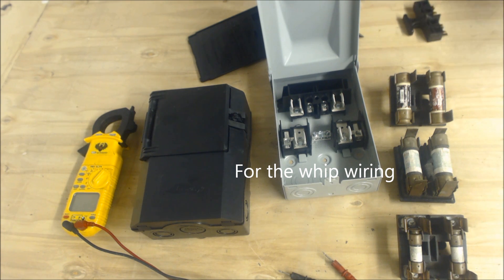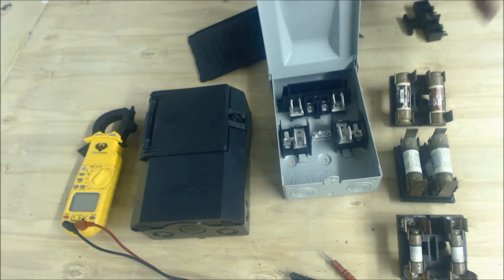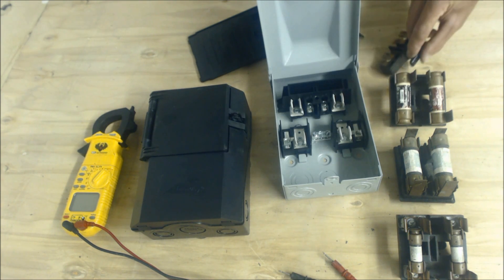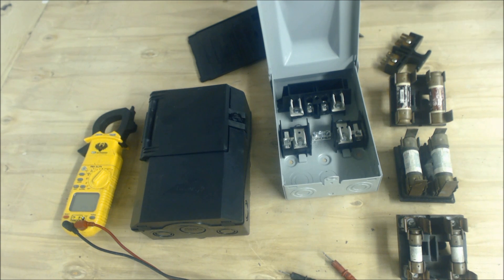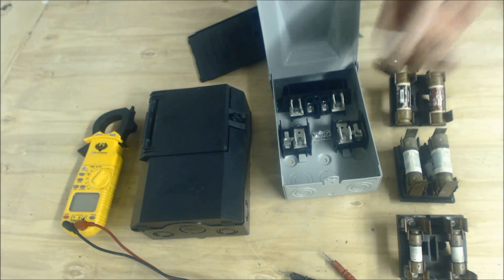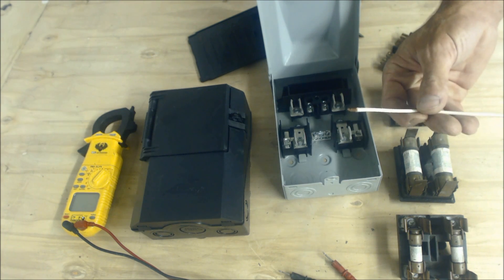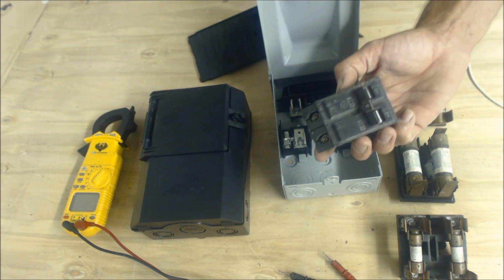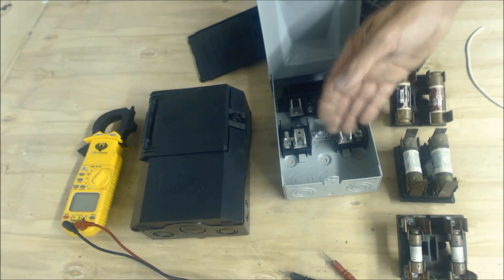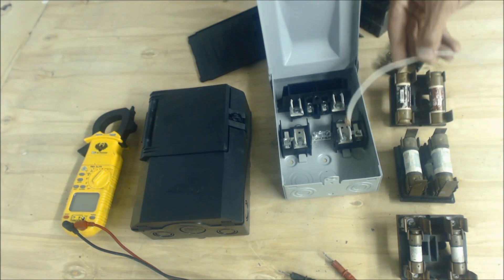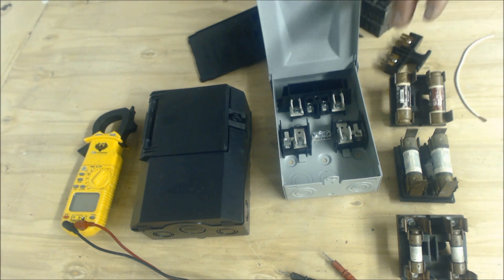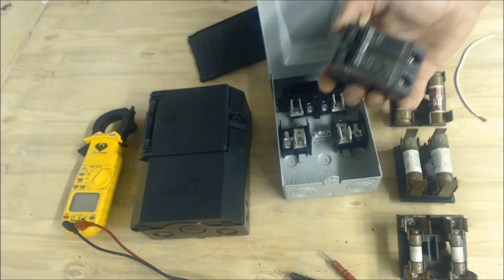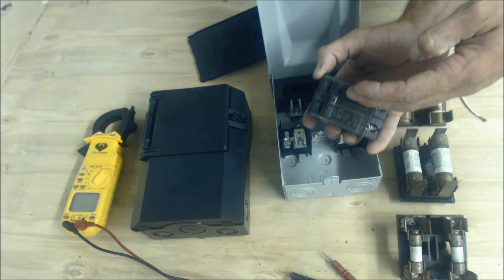So you just want to make sure you're working with a correct wire size. In some instances, when it's not fusible disconnects, and it's just a disconnect, non-fusible disconnect, sometimes, like they say, you can use a lower wire size, but I would always recommend that you use the same wire size as the breaker, or pass that at the fuses. After that, the same size as the fuses. It's important to use the proper fuses or the breaker and have the proper wire gauge size.